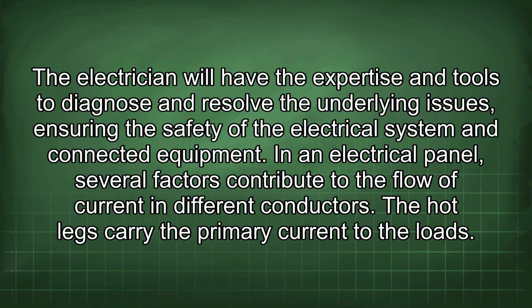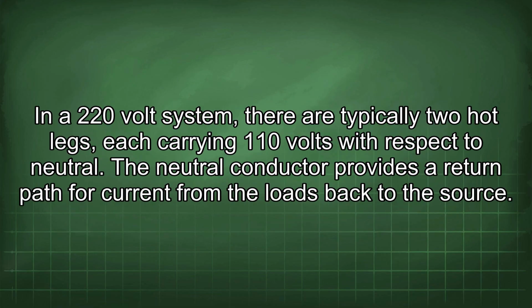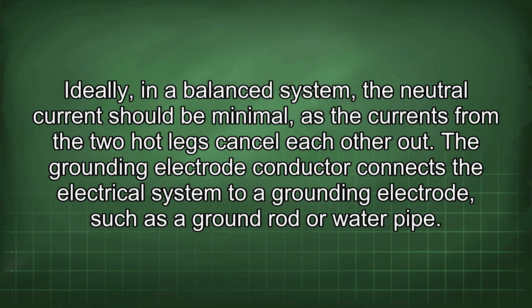In an electrical panel, several factors contribute to the flow of current in different conductors. The hot legs carry the primary current to the loads. In a 220 volt system, there are typically two hot legs, each carrying 110 volts with respect to neutral. The neutral conductor provides a return path for current from the loads back to the source. Ideally, in a balanced system, the neutral current should be minimal as the currents from the two hot legs cancel each other out.